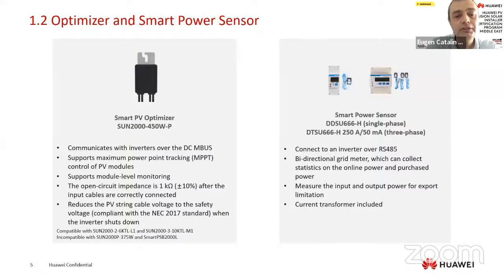Compatibility: we already know single phase 2-6 KTL-L1 and 3-phase 3-10 KTL-M1 and other inverters but in another area, in commercial area. As smart power sensor in this solution, we will use single phase and 3-phase smart power sensor, of course. Communicate with inverter through RS485. It is a bidirectional grid meter, measuring input and output power for export limitation, and the current transformers are included in the package.